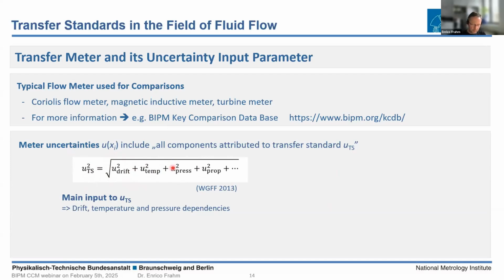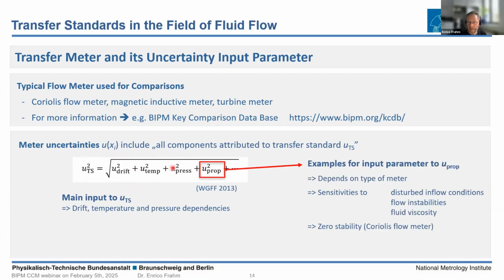And other additional input parameters could also be discussed and depend on the type of meter. Like sometimes a meter is more sensitive to disturbed inflow conditions or to flow instabilities and fluid viscosities. Another example, for a Coriolis flow meter, it's very sensitive or could be more sensitive to zero flow stability of the meter itself. So a detailed estimation of all of these input parameters is a very important keystone for a reliable comparison.